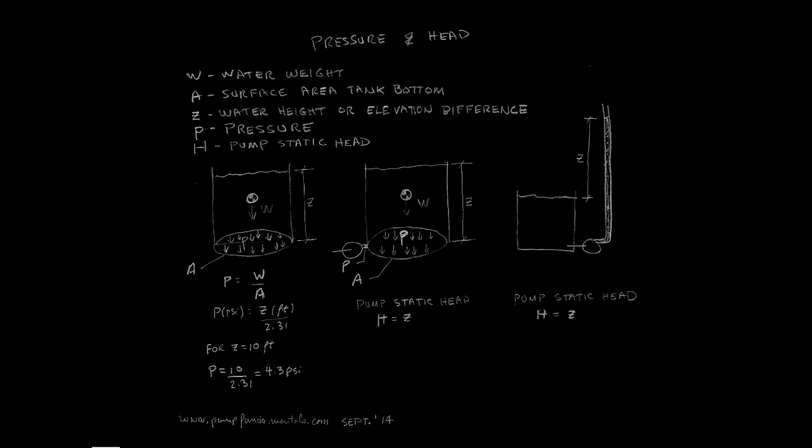How does pressure relate to pump head? Head and pressure are two facets of the same coin — you don't have one without the other. If we take a tank with a certain amount of water, the weight of water gets distributed over the tank bottom. This weight distribution against the surface is pressure, equal to the weight divided by the surface area. Using typical imperial units, the pressure value is the height Z in feet divided by 2.31 for water, with pressure in psi or pounds per square inch.